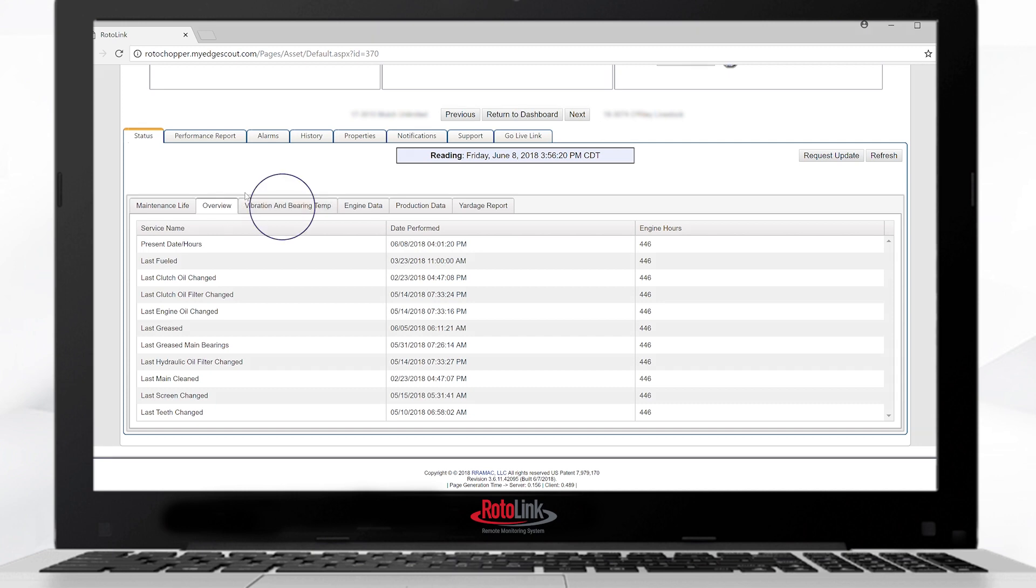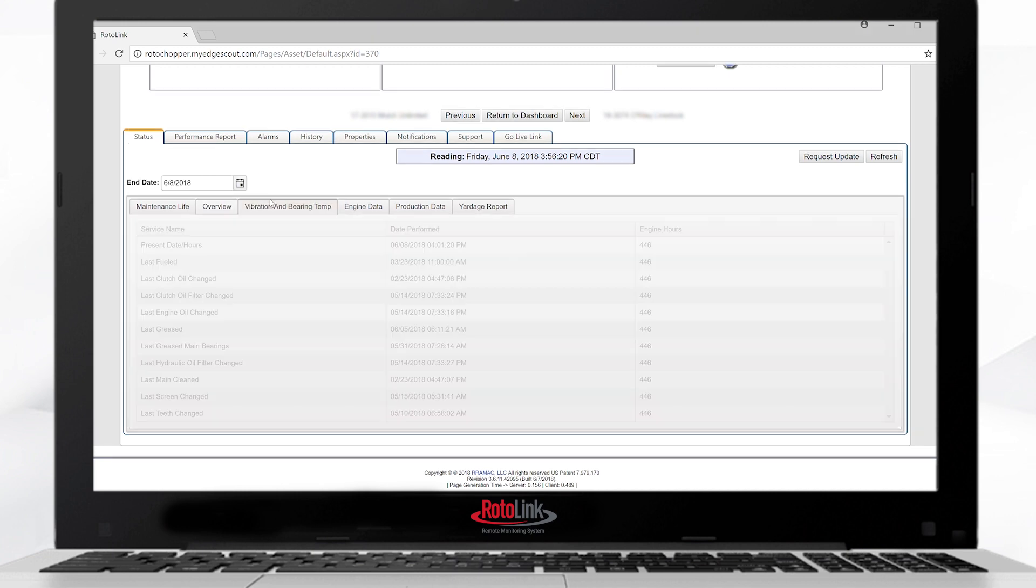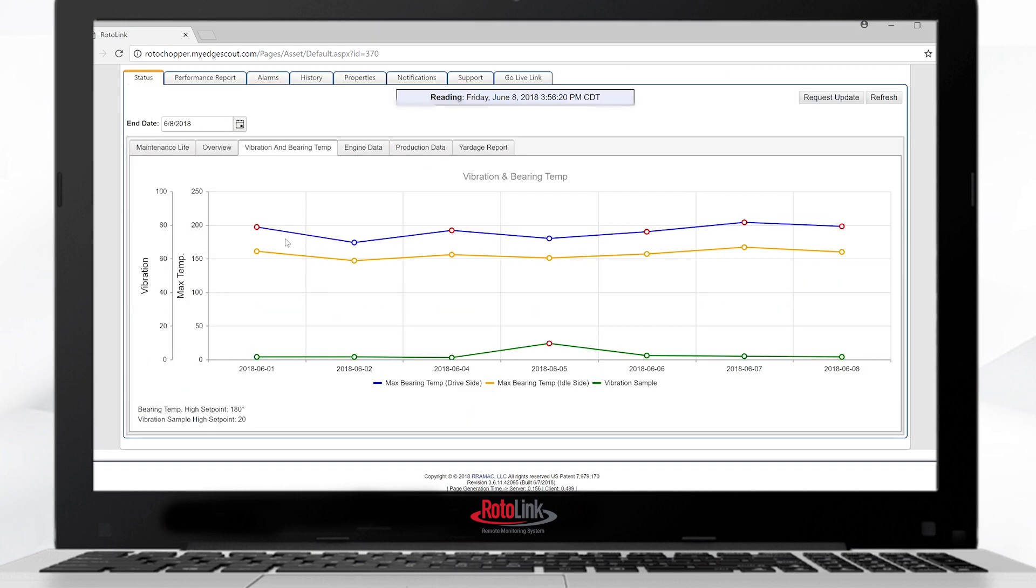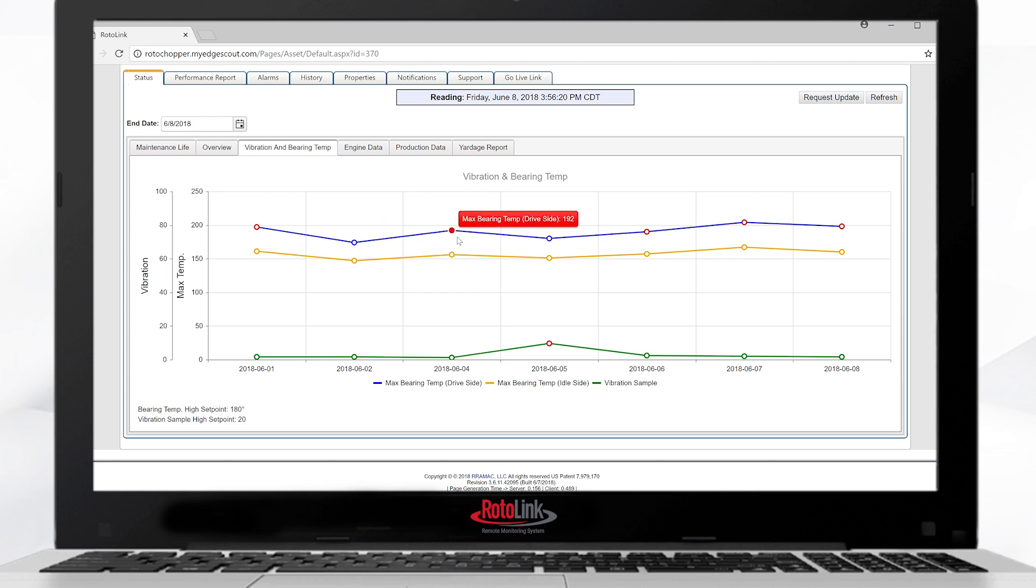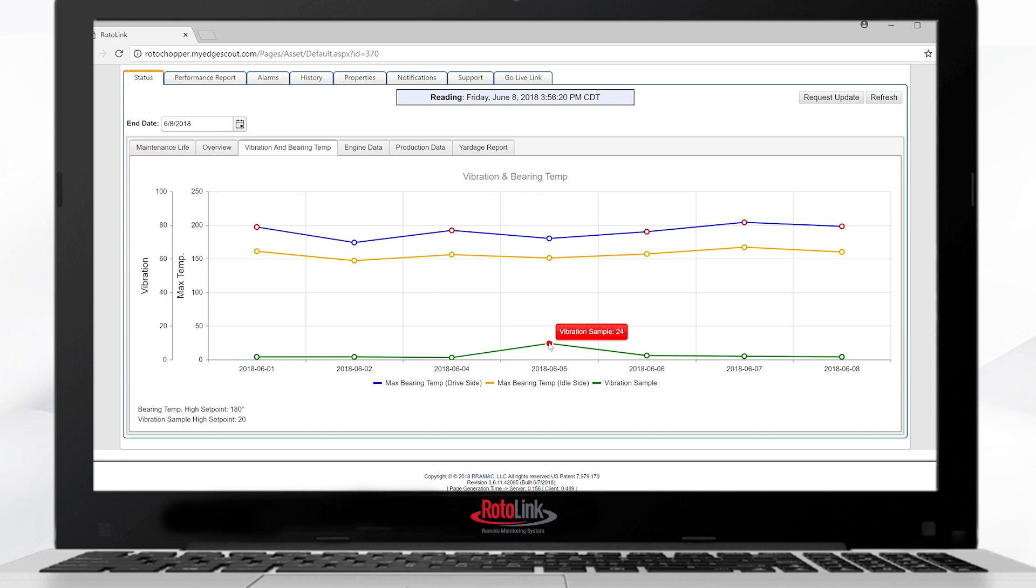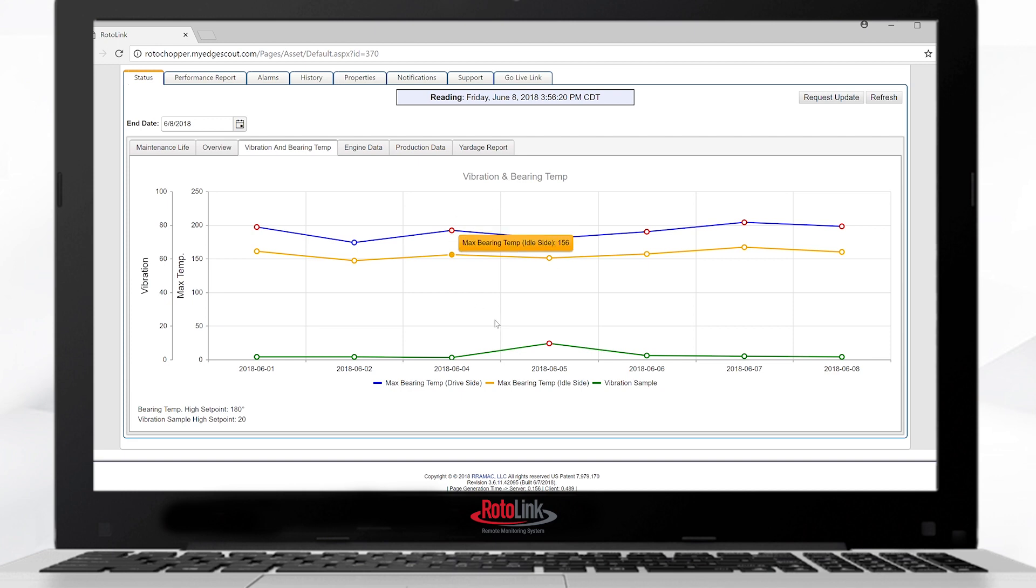Select the vibration and bearing temp tab to see the rotor vibration and bearing temperatures. Vibration readings are selected at the beginning of the day and stored. Hover the mouse over the top of the markers to see exact values. The vibration is also taken on a daily sample. Any values greater than 20% will show in red. Any temperature values greater than 180 degrees will show in red.